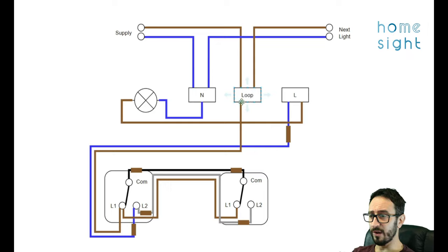So we've got our live coming from here on our brown cable onto our L2. Now you can see that at the moment that is connected to our common so if we follow that up with our electricity coming through this common coming back to our L1 back along this brown wire and ultimately back to our L1. So what we haven't done is we haven't completed our circuit and put live electricity down this blue wire onto our switch live and ultimately to our bulb.